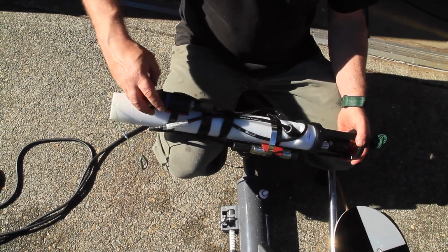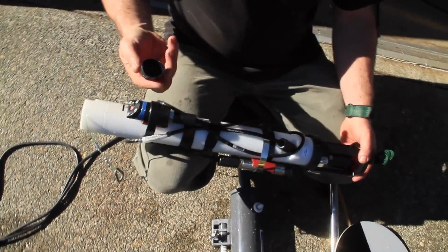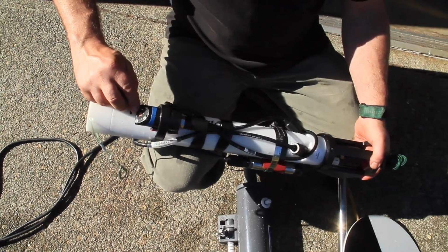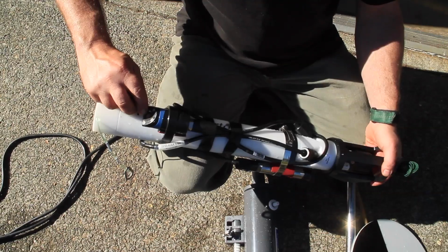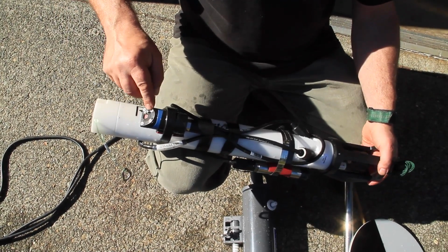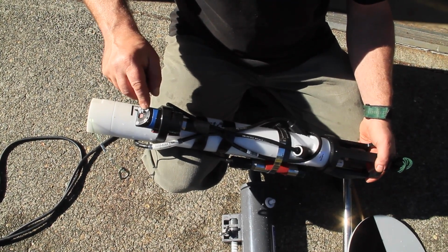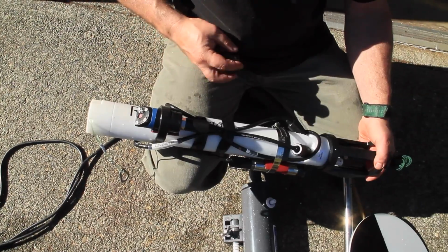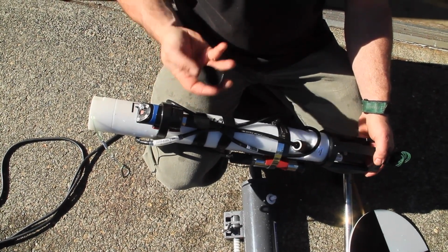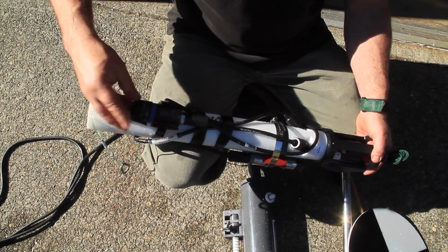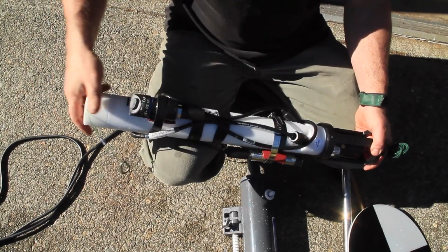So the oxygen sensor has a cap on it. The cap should be moist. There's this window here, that's the actual sensor part of it that measures the oxygen concentration. This little nubby here is a temperature sensor, it's temperature compensated. Okay, make sure that the cap is wet when you put it back on. The membrane likes to be a little bit wet. Okay.